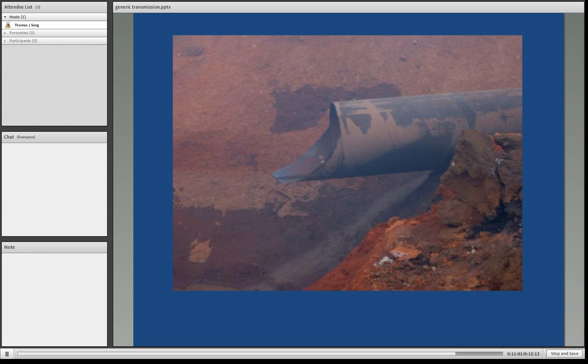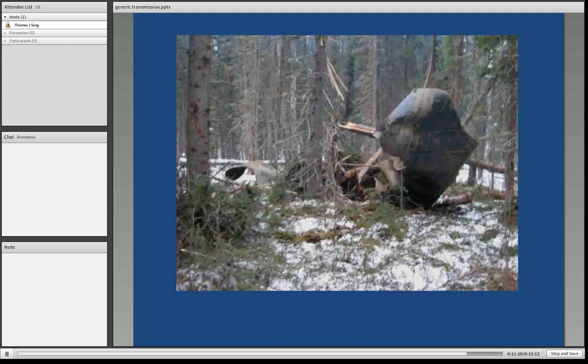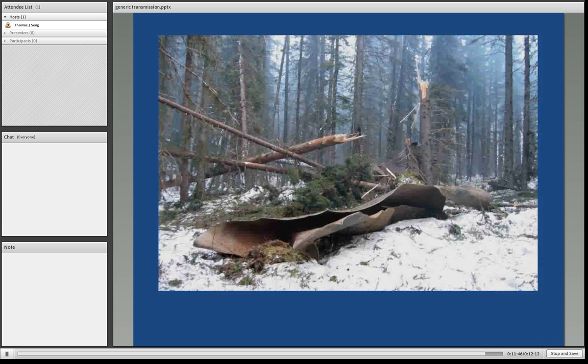This is where the pipe was welded to the next section of pipe and the weld actually gave way. This is the scorched earth that was in the area around this particular explosion. This is an actual piece of the pipeline itself — the tube, as we call it. The steel sheets are actually rolled into those pipe sections horizontally and then the weld is done on the circumference when the pipe sections are joined together. This is an actual rolled piece of pipe that was part of this explosion and blew right out of the line.